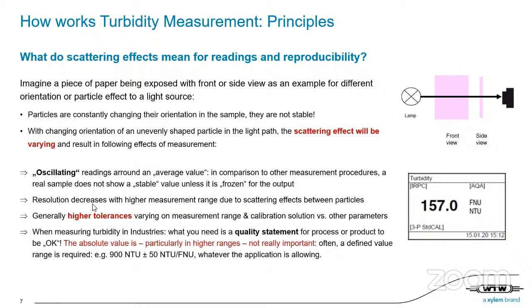The more particles are in the solution, so in higher ranges, the lower the resolution and tolerance given. So actually in drinking water, we can measure with an accuracy of 0.01 NTU because we have few particles and the light is going to the detector. Particles are usually relatively small. In wastewater, for example, they are bigger. And the higher the particle number in a solution is, the more scattering there is between the particles. Therefore, the tolerance becomes higher and the resolution coarser. So for example, we have 157 NTU instead of 157.01 NTU. And if it comes to the very high range, we do not even give a digit after the point.